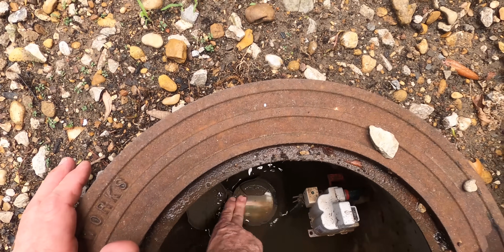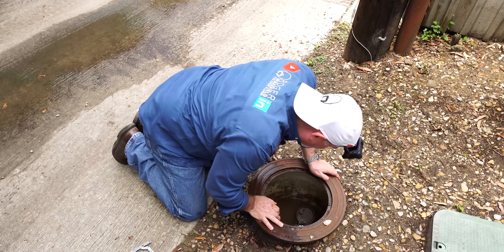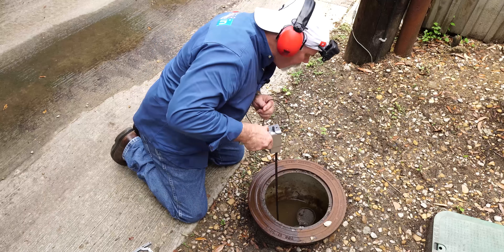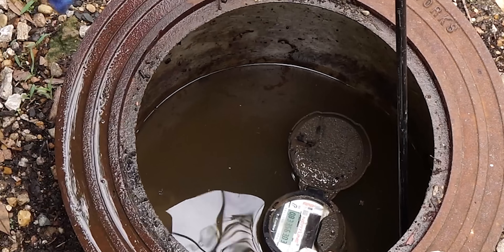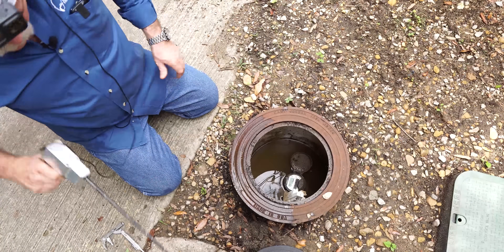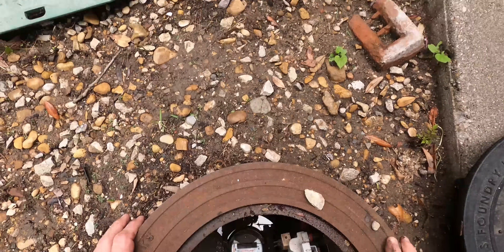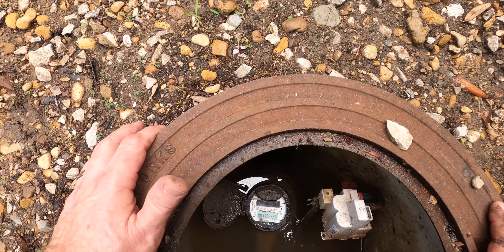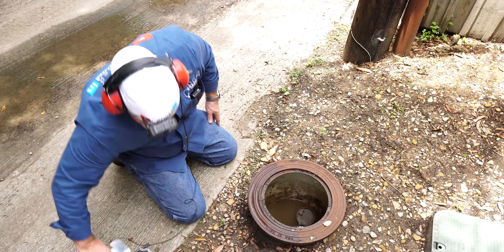So what I'm doing is watching this digital meter and trying to see what it's showing. Right now it's showing zero GPMs — zero water flow whatsoever. I'm going to go ahead and listen just to see what's happening. It's bouncing a little bit — I'm getting a little bit of movement and just a little bit of noise. It's not very loud, so I can't tell if it's just white noise. Right here I'm reading 0.00, but every now and then it'll jump up to 0.33. So that tells me there may be just a little bit of water movement, but if there is, this is a tiny leak.